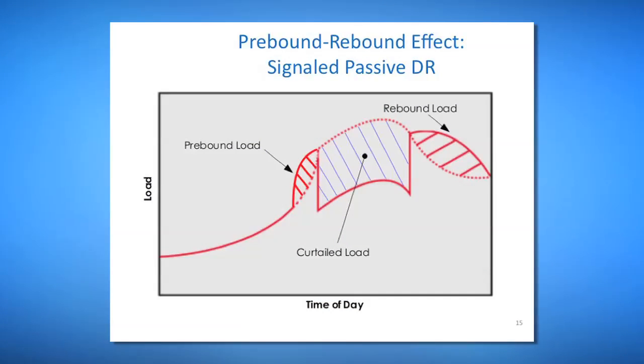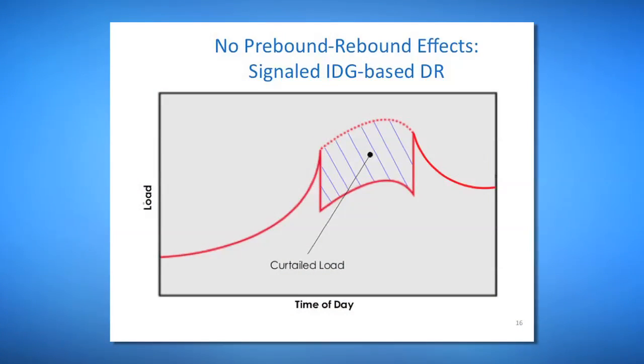As far as pre-bound and rebound, when you do demand response right now, as a facility you sit there and hit the chillers, hit the heat, or alter process. When you do it, sometimes you get a pre-bound effect where you load up before, and then after the event takes place, you load up again. When you use the DG, or the IDG, to get the job done, there's no pre-bound or rebound. You just soft load and soft unload later. So it's very nice for the utility system as well as the facility, avoiding pre-bounding, rebounding, and changing operations to get this done.